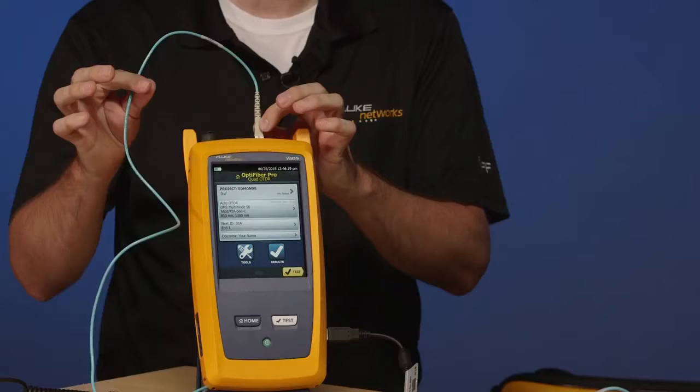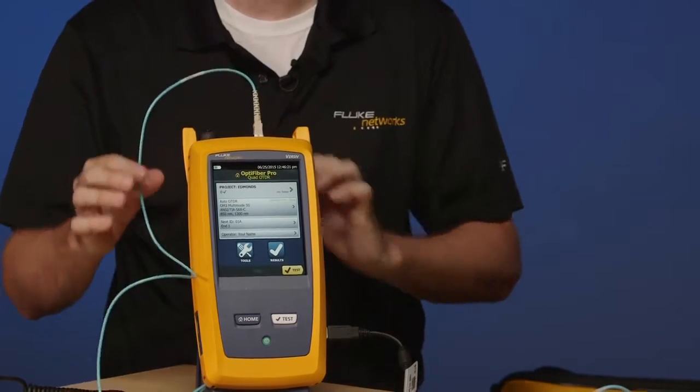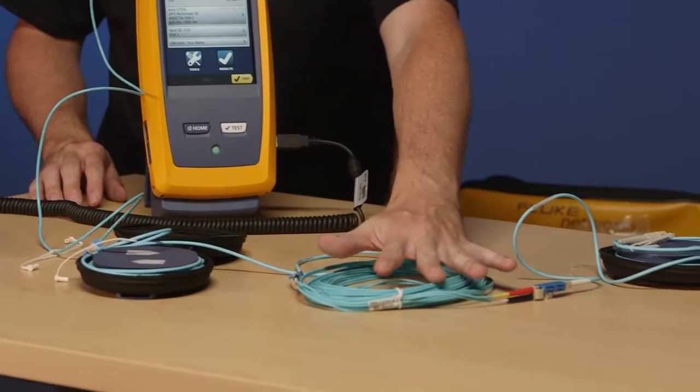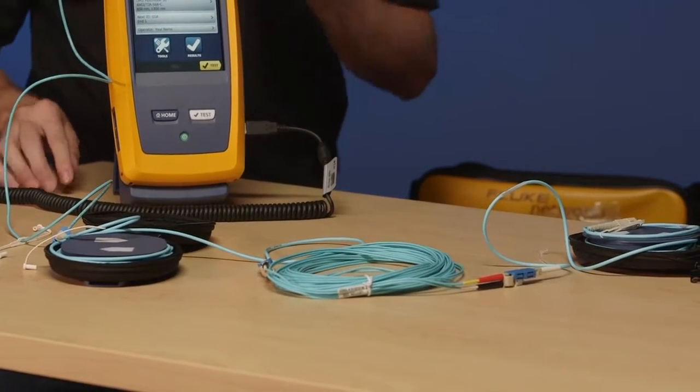So with our launch compensation set, we're ready to run a test. What I've got here is a little sacrificial OTDR port fiber. We'll talk about that in a moment and the reason why I'm doing that. I've got my launch fiber, I've got my tail fiber, and I'm connected to my link under test. And for those of you who saw that OptiFiber Pro video I did, this is the same fiber that I'm testing, and there's a good reason for doing that when I download the results later on.